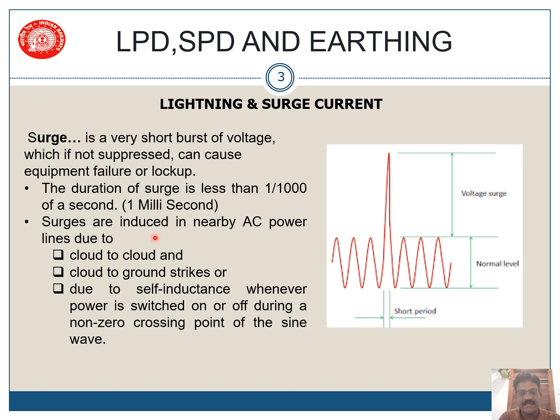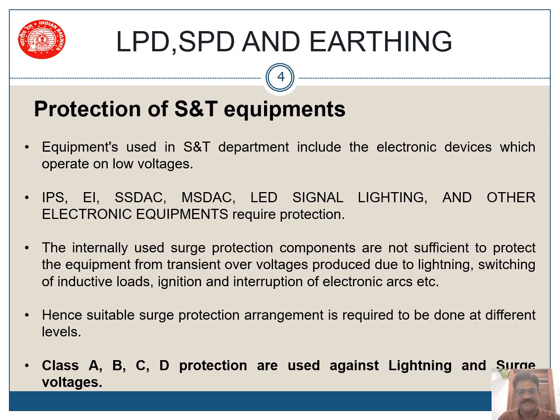Surges are induced in nearby AC power lines or even in our cabling lines, basically whenever there is any cloud to cloud burst, cloud to ground strike, that is lightning which comes from cloud to ground, or due to self-inductance whenever power is switched off and on, due to non-zero crossing point of a sine wave. So whenever you switch on any power supply, a sudden increase in voltage can result in a fuse blowing off also. That is also a type of surge.